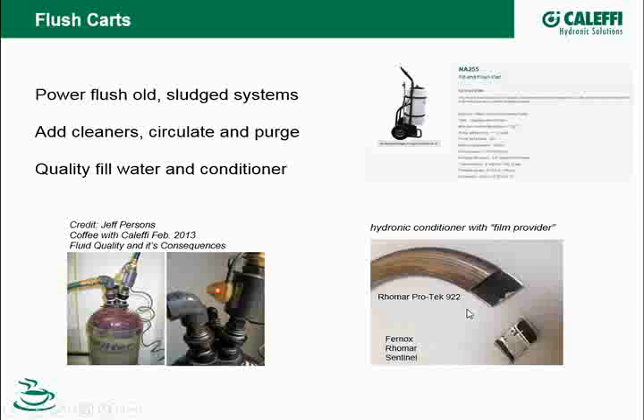And basically, one of the ingredients in these corrosion inhibitors is a film provider. And so when I cut this apart, I took my hacksaw, and after I cut the tube out of there, I cut a little window out of it so I could see inside. And you can see I took my knife and scratched it off after I cut it open, and that's the little film that the film provider, one of the ingredients in the corrosion inhibitor, actually put on the bare stainless steel tube. So instead of just having bare stainless or bare copper, whatever metal the heat exchanger is made out of, it puts a very, very thin film. It's almost like if you take a little skin off your thumb when you nick it, it's that thin of a layer.